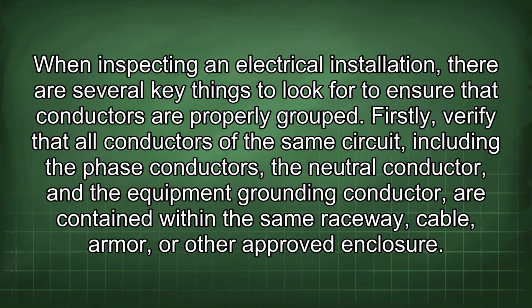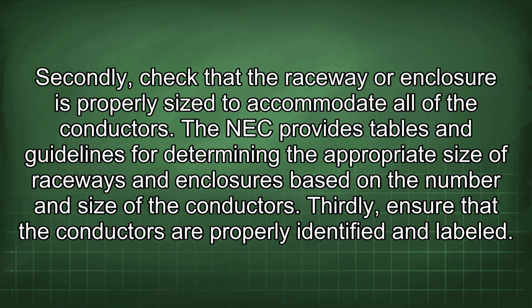When inspecting an electrical installation, there are several key things to look for to ensure that conductors are properly grouped. Firstly, verify that all conductors of the same circuit, including the phase conductors, the neutral conductor, and the equipment grounding conductor, are contained within the same raceway, cable, armor, or other approved enclosure. Secondly, check that the raceway or enclosure is properly sized to accommodate all of the conductors. The NEC provides tables and guidelines for determining the appropriate size of raceways and enclosures based on the number and size of the conductors. Thirdly, ensure that the conductors are properly identified and labeled.